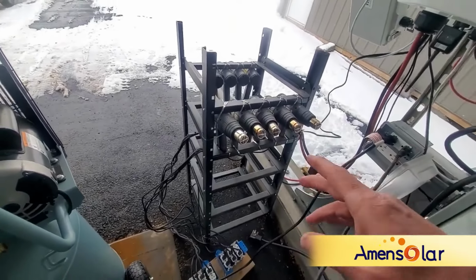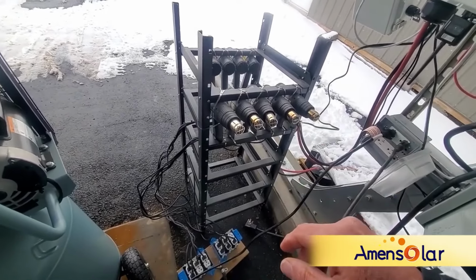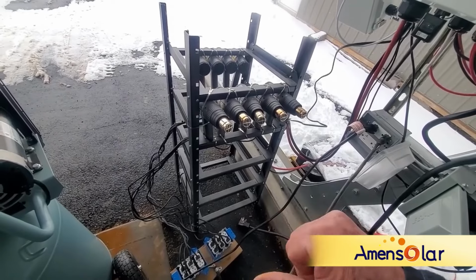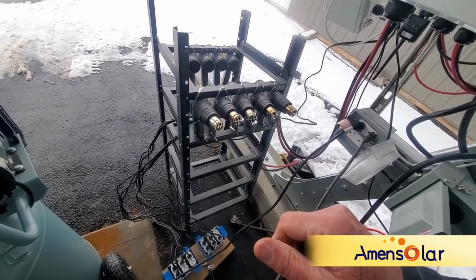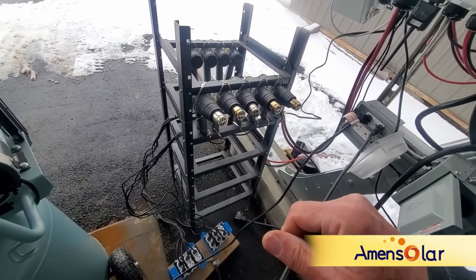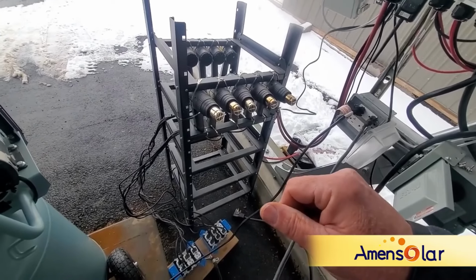So the test we're going to do now is run some heat guns, because it's easy running a split phase unit. Most guys, when they do a test, run everything on 240 volts, balancing the phases, but we're going to not balance the phases in this case.